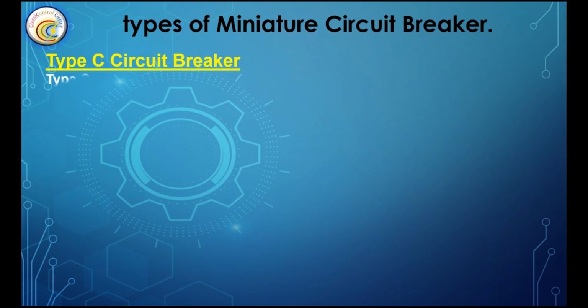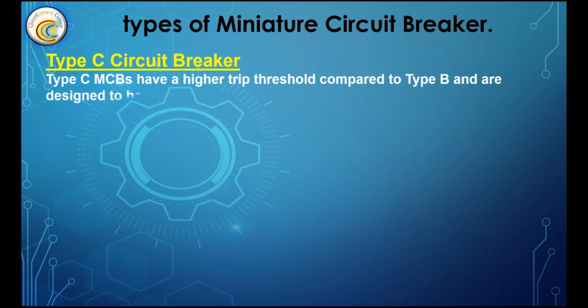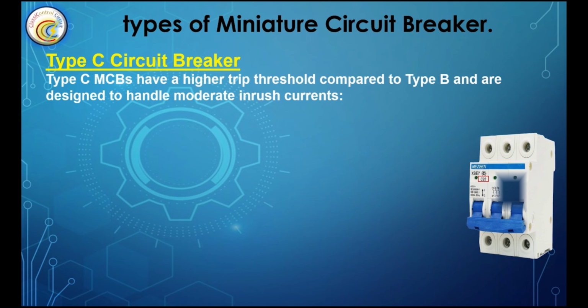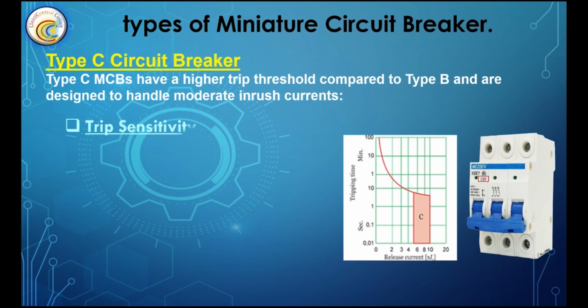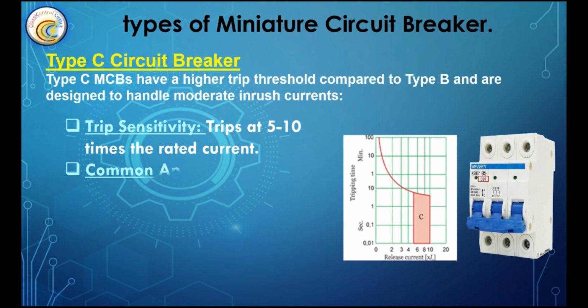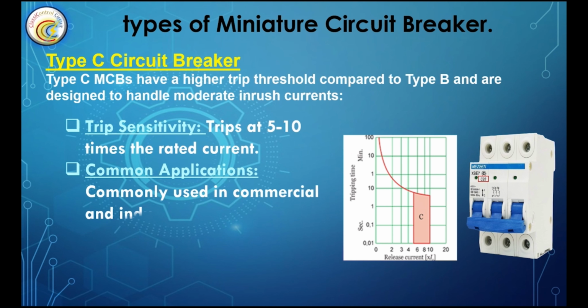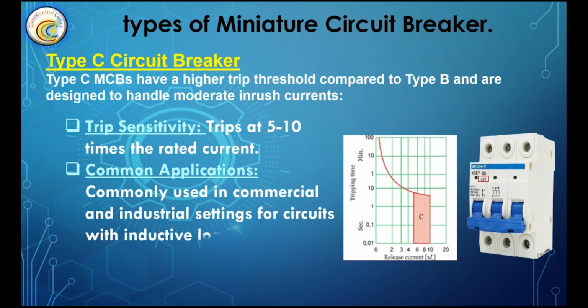Type C circuit breaker. Type C MCBs have a higher trip threshold compared to Type B and are designed to handle moderate inrush currents. Trip sensitivity: trips at 5 to 10 times the rated current. Common applications: commonly used in commercial and industrial settings for circuits with inductive loads, such as motors, transformers, and fluorescent lighting.